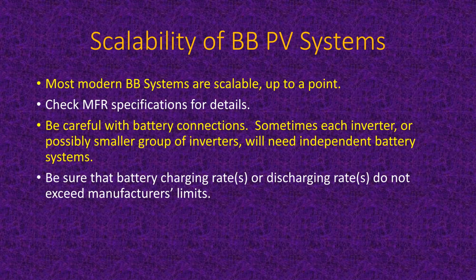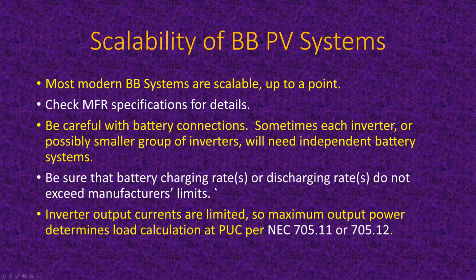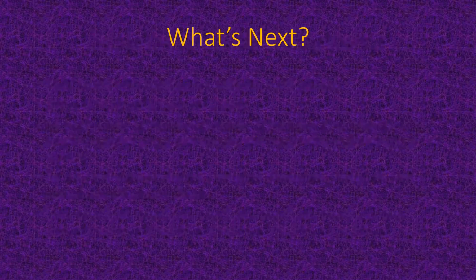So, and another thing you watch for with the scalability of the systems. And inverter output currents are limited, so the maximum output power determines the load calculation at the point of utility connection, and that is National Electrical Code 705.11 or 705.12. Okay, a couple of code references there.